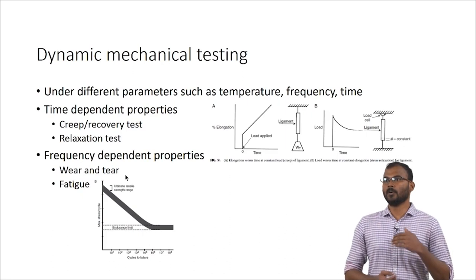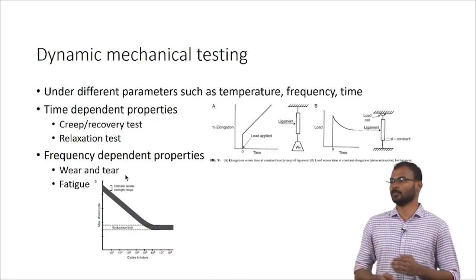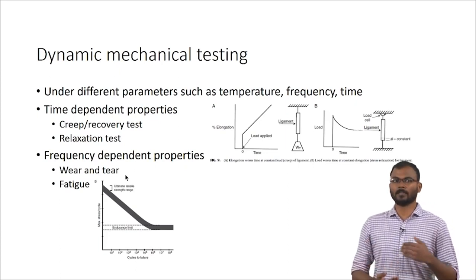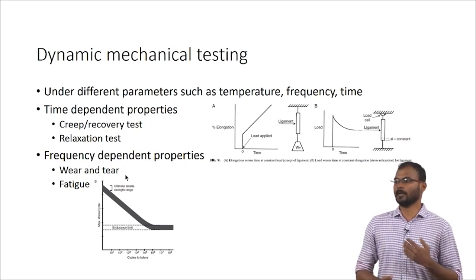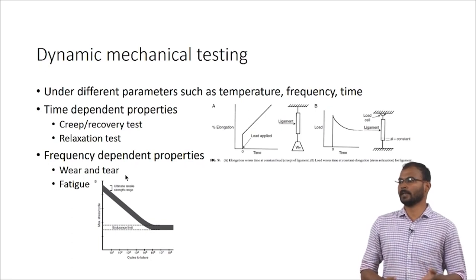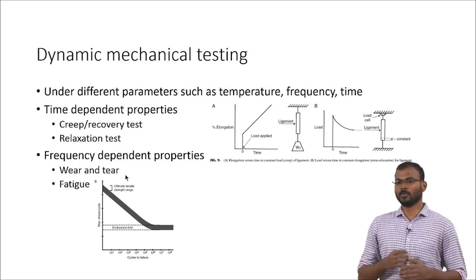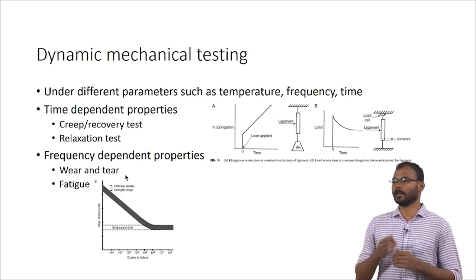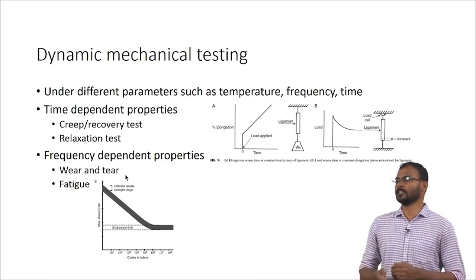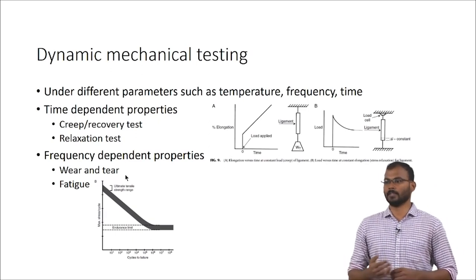Frequency is how many times a material is being used for that specific application. Consider a hip prosthesis — how much distance you walk affects the frequency. Consider heart valves: they have to beat around 72 times per minute. Over a day, a year, and a prolonged period, the valve has to open and close an enormous number of times. Over those periods, the material is in contact with nearby surfaces, causing corrosion, surface etching, and erosion that reduce the efficiency of the material. Those factors have to be tested before clinical use.